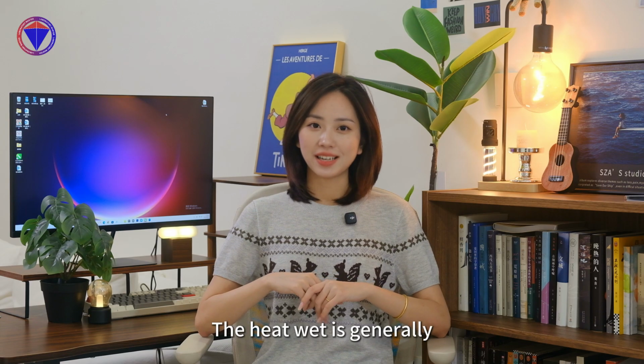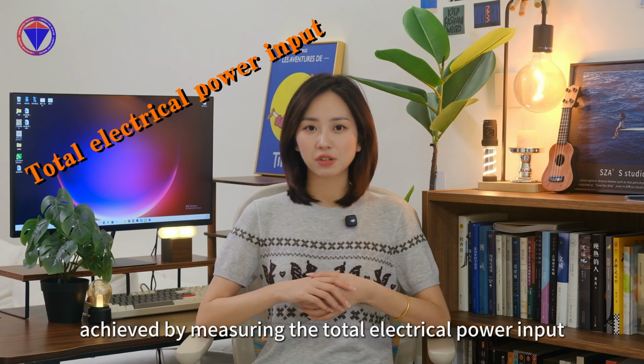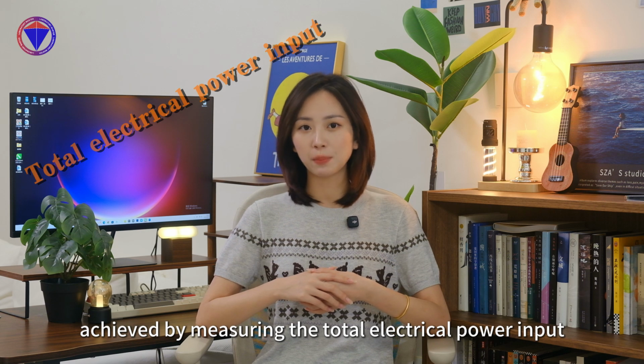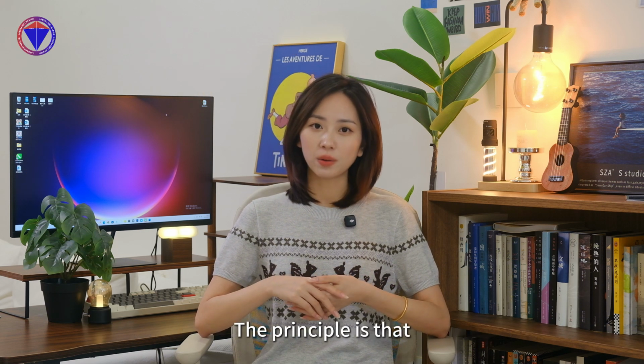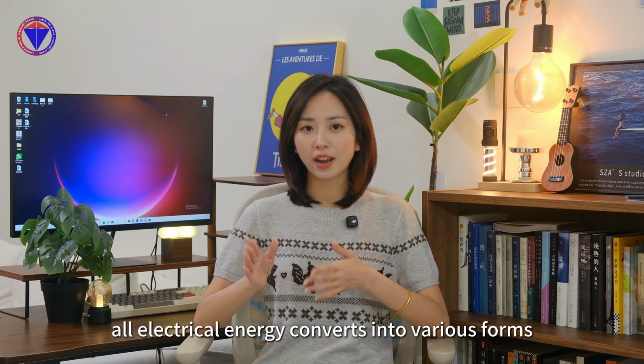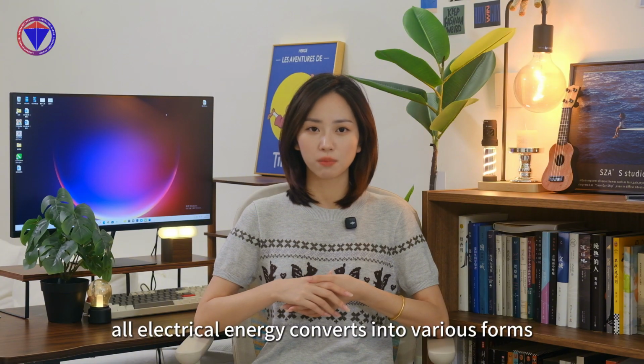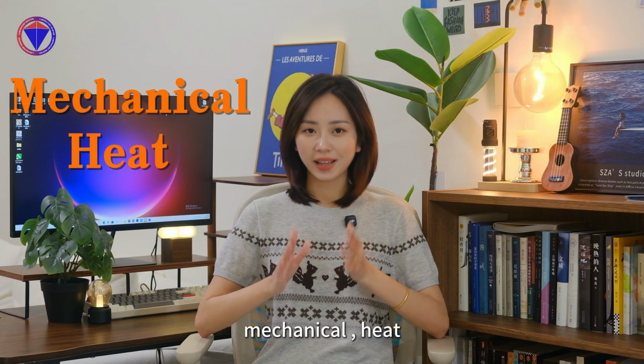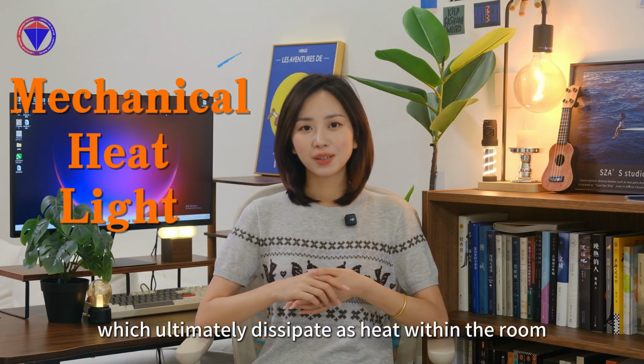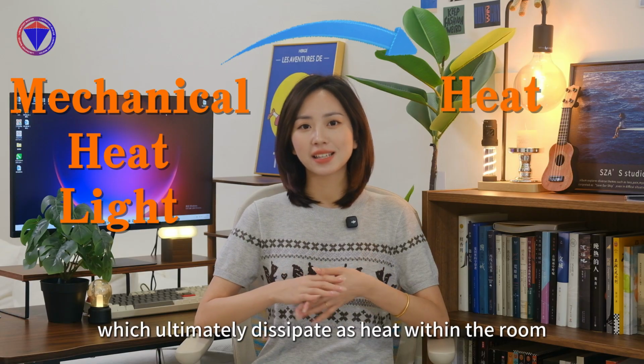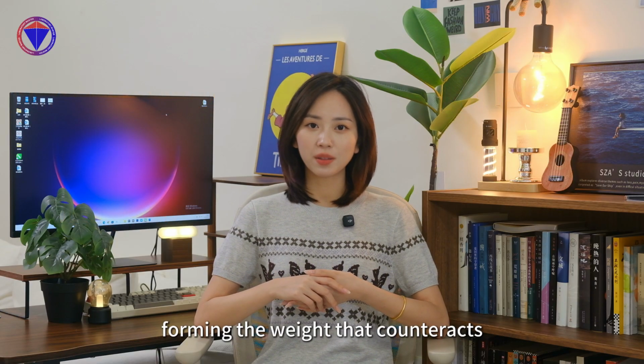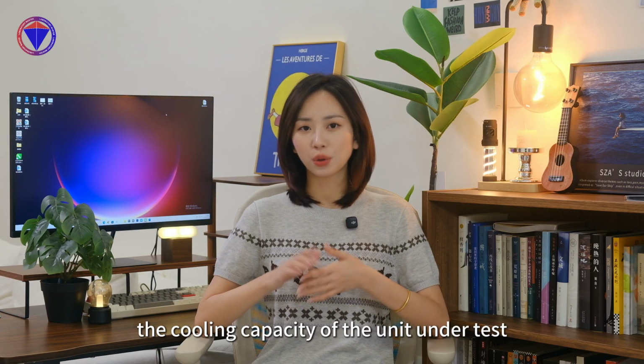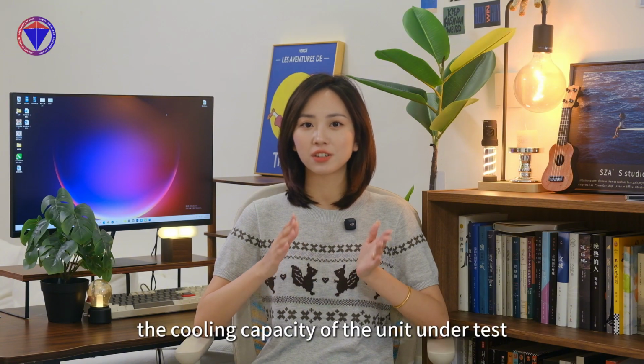The heat weight is generally achieved by measuring the total electrical power input into the room. The principle is that all electrical energy converts into various forms of energy, mechanical, heat, light, etc., which ultimately dissipate as heat within the room, forming the weight that counteracts the cooling capacity of the unit under test.